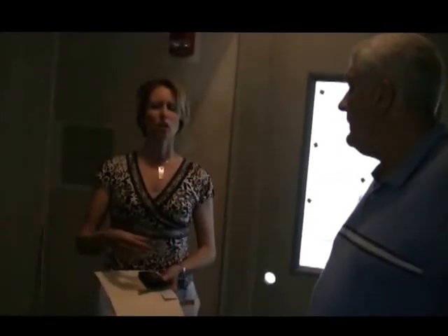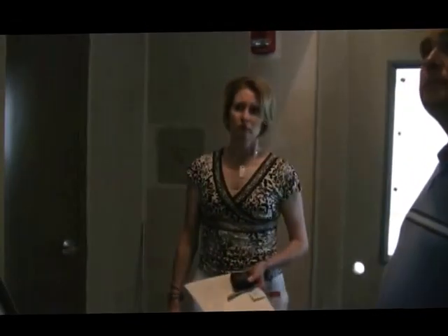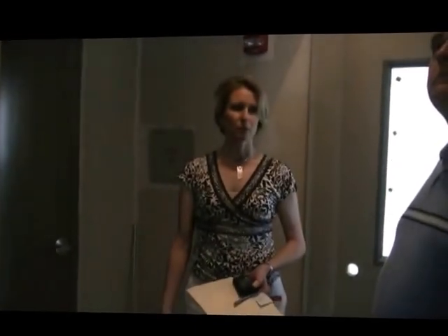The software will send out a soft, medium, or hard failure. A hard failure, we know it's shut down, and that takes priority. We still want you to call us; it doesn't replace that, it's really just an extra system. A soft failure is something that is not going to shut the elevator down and we can get to on our next maintenance visit, but it alerts us that this needs to be looked at. Medium is a little more immediate: we're actually able to prevent shutdowns when we know something is falling out of its operating parameters for a given function. Great. It's much more high-tech than elevators of the past, yeah.